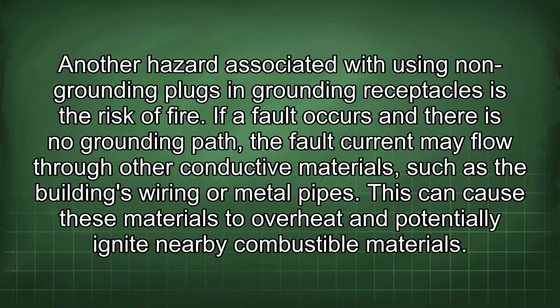Another hazard associated with using non-grounding plugs in grounding receptacles is the risk of fire. If a fault occurs and there is no grounding path, the fault current may flow through other conductive materials, such as the building's wiring or metal pipes. This can cause these materials to overheat and potentially ignite nearby combustible materials.